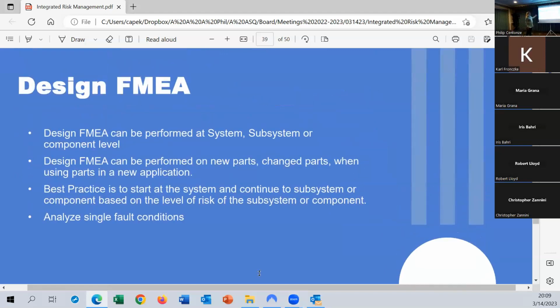In the design FMEA, again, we look at parts and how the different items can fail. Design FMEAs are really useful if you're using a new part that you don't have any history on. If you're changing the application of something you're already using, you want to look at your design FMEA to make sure that it's still going to be fit for its intended function. In an FMEA, you are analyzing single fault conditions. When you're doing it at the system level in a risk analysis, you're looking at a sequence of events, so it could be multiple things going wrong at one time.